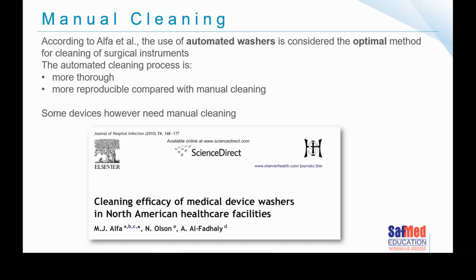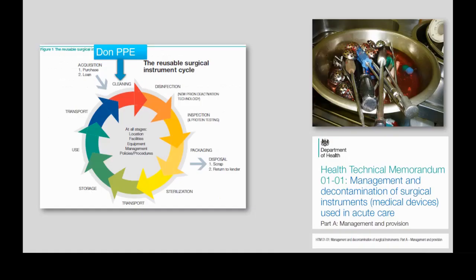As I was saying, in this paper that Alfa published in 2010, the focus was on understanding why automated washer disinfectors are so important, although some devices do need to be cleaned manually. To make an instrument safe to use on a patient, that device needs to go through a whole series of steps: cleaning, disinfection, inspection, packaging, sterilization, safe transport, use, and safe transport again of a contaminated device. The entire process begins at the very beginning — around cleaning.